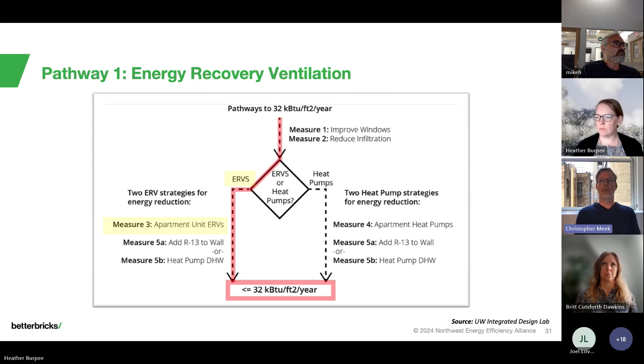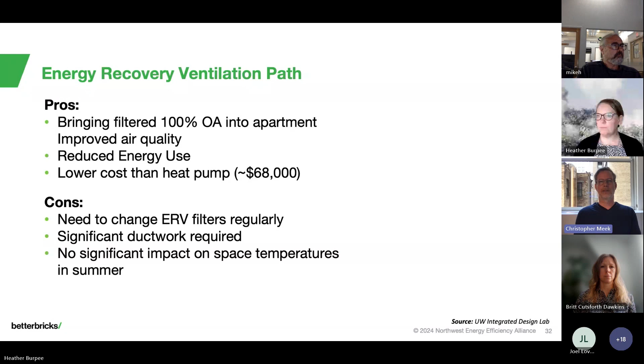The advantage is that we're now providing 100% filtered outside air into the apartments, which is nice during smoke weeks in Seattle, and that improves indoor air quality, at a significantly lower cost than heat pumps. The downside is we have to change the ERV filters regularly, add some ductwork, and we don't get the benefit of cooling since we haven't added that capability.